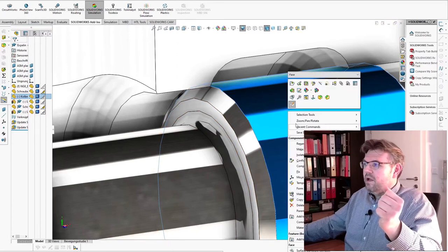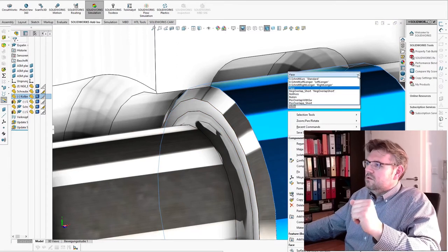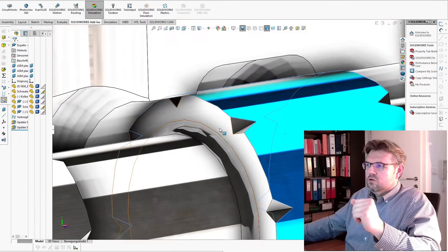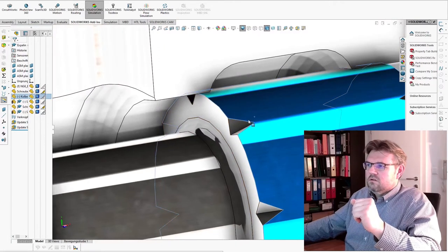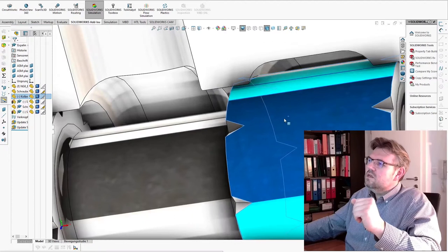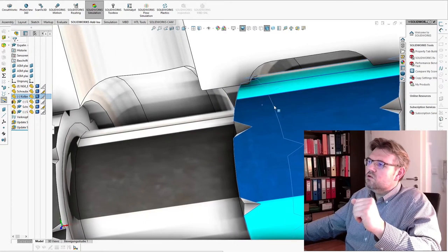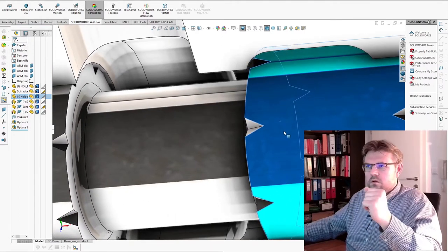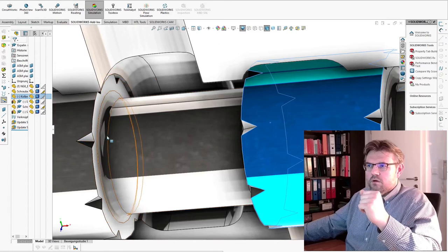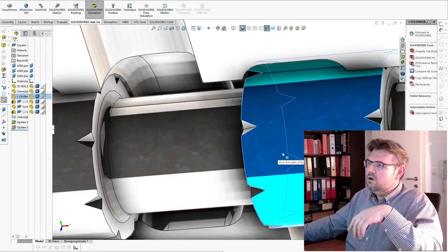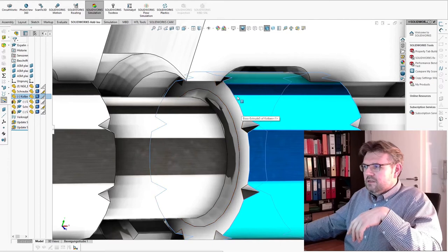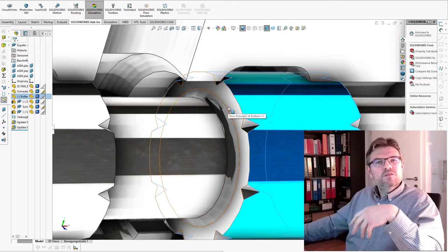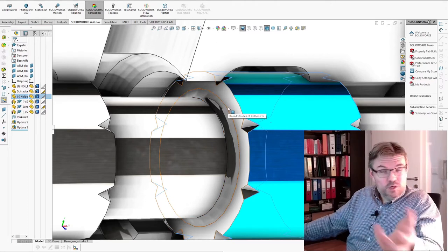There might not only be these things, there might also be some notches inside. Now it's sealed, then only a small part is open. This small part will be more and more, and then full. See, there are notches around this piston. So with the styling of the control edges, I can also influence the flow characteristic during switching of the valve. Okay?